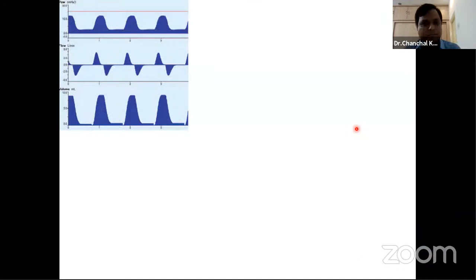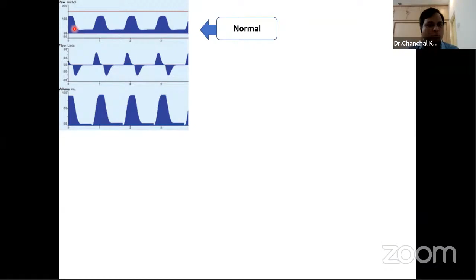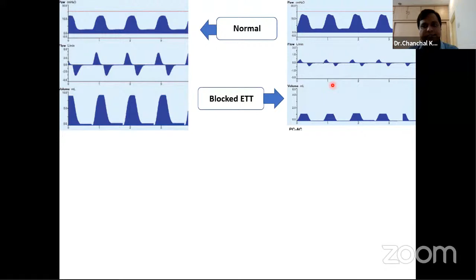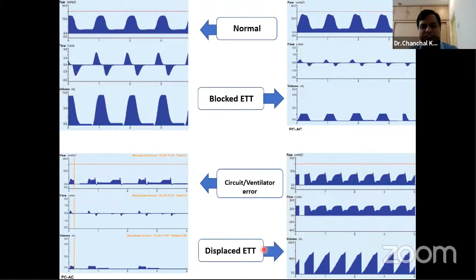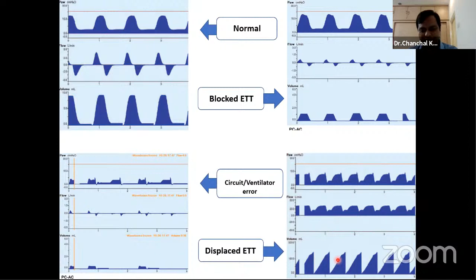So comparing the graphics, this is a normal graphic, normal ventilator graphics, where you can see that there is a normal and regular pressure, flow, and volume waveform. In case of a blocked endotracheal tube, one may find that the pressure waveform will be regular, but the flow and volume waveform will be reduced in size. And on display, one may find reduced actual tidal volume and minute ventilation. If there is a problem with the circuit or ventilator, then all three waveforms will be irregular. And if there is accidental extubation, then one may find that the pressure waveform will be regular, but in the flow waveform, there will be absent expiratory flow, and there will be a 100% leak in the volume waveform, as we saw in the first case scenario.